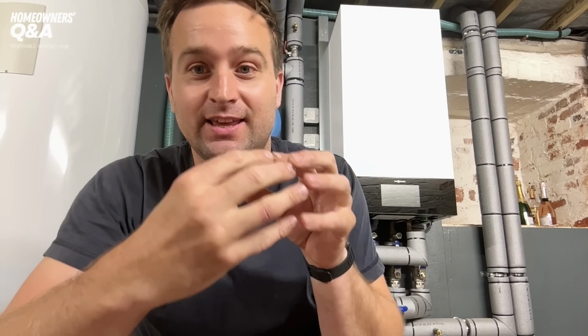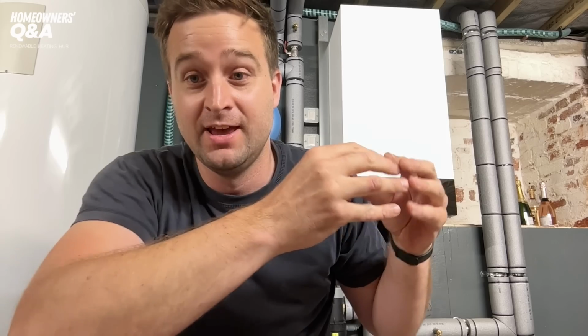So if I shut down radiators 1 through 9 and left number 10 as the only one open, would that then get the full 45? Yes. Okay, I know what you're saying. It's a difficult concept, but because what Brendan says is the energy, the heat required, the way it gets to the radiator is through flow. So the two things are intrinsically linked.